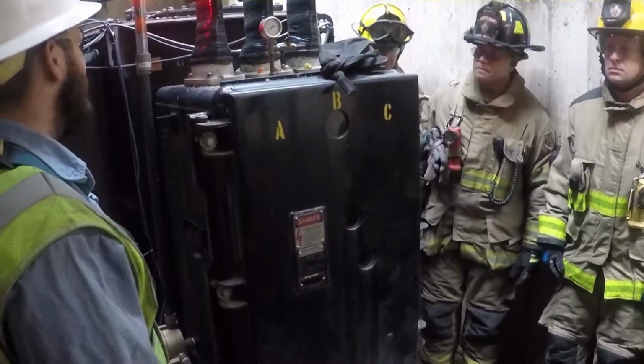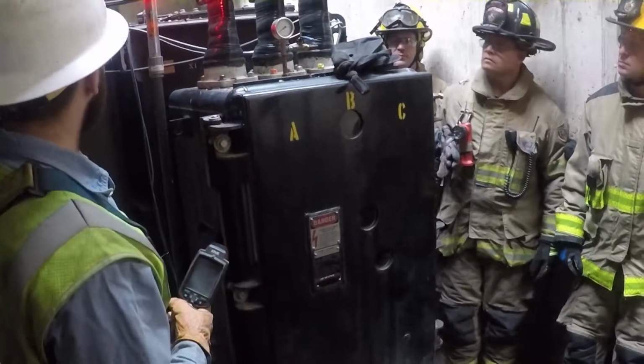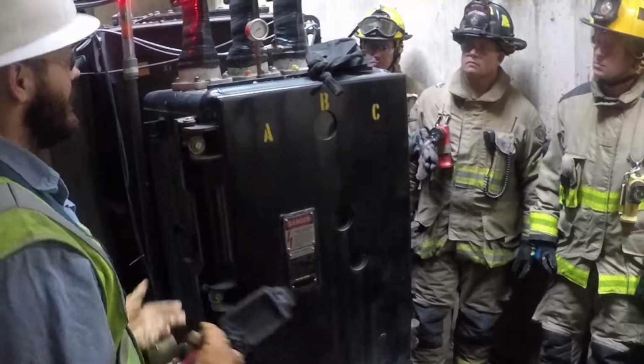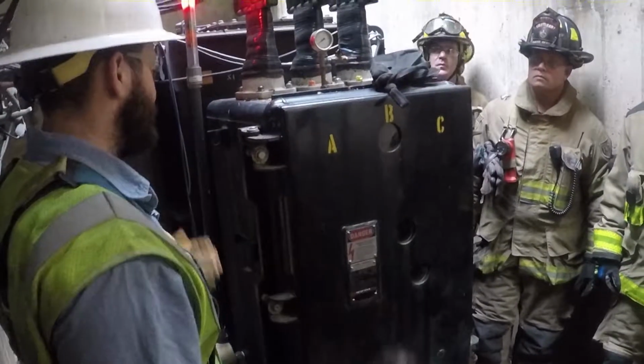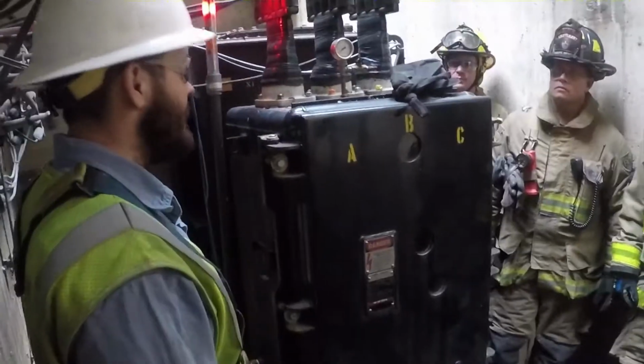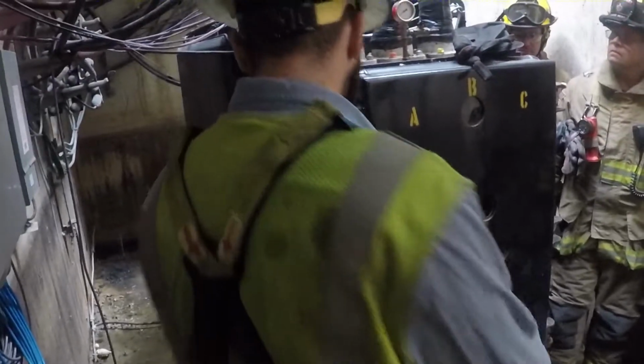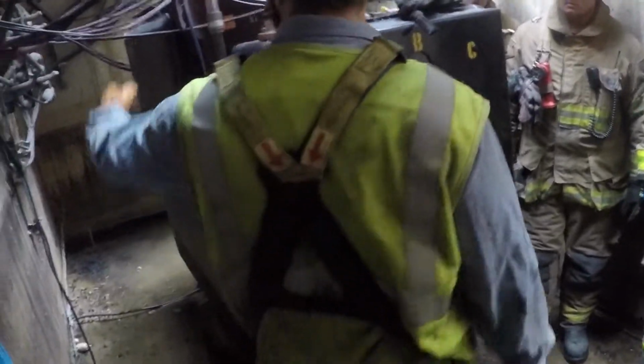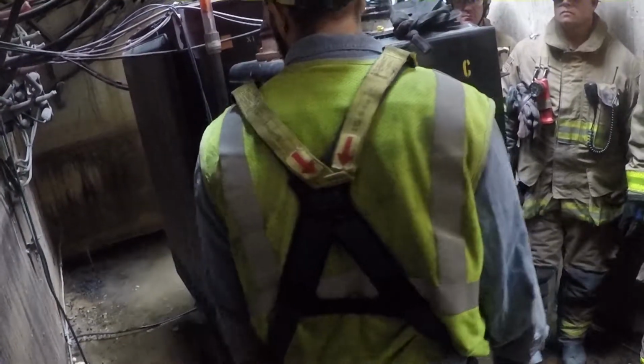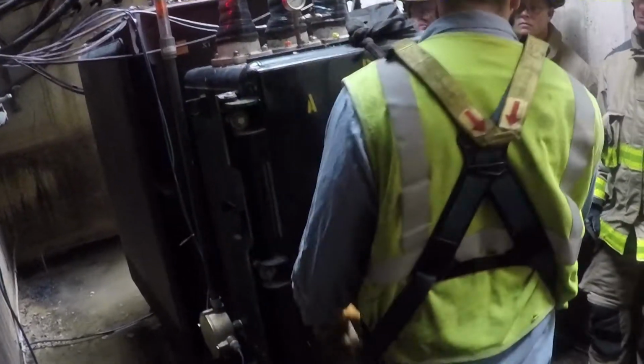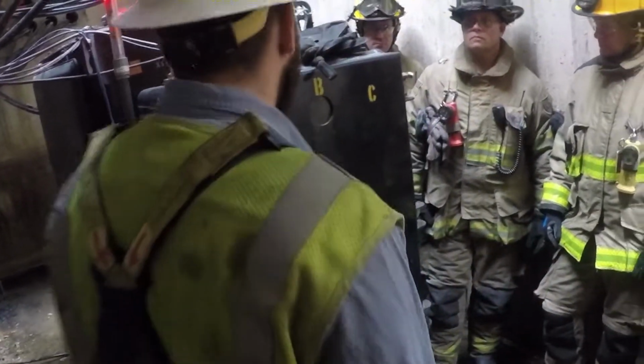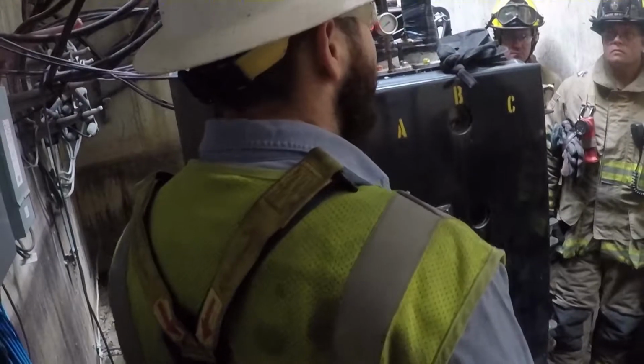One thing about a network is, say you cut this, it's going to be hot at both ends because it's basically a grid, so it's always going to be hot at both ends. So if something were to happen and there was a cable down here that was exposed, opening this wouldn't de-energize it. It would just prevent back feed on that part of the circuit.